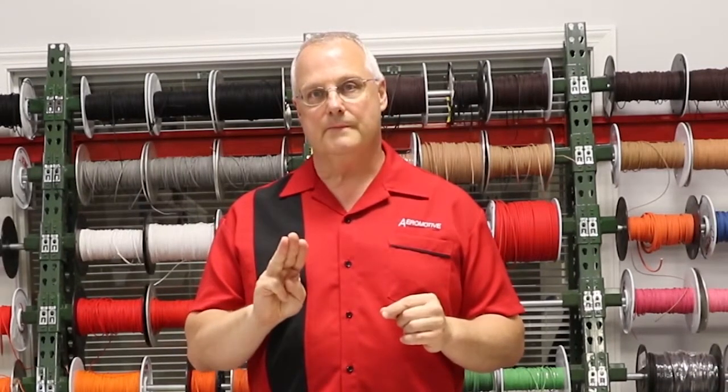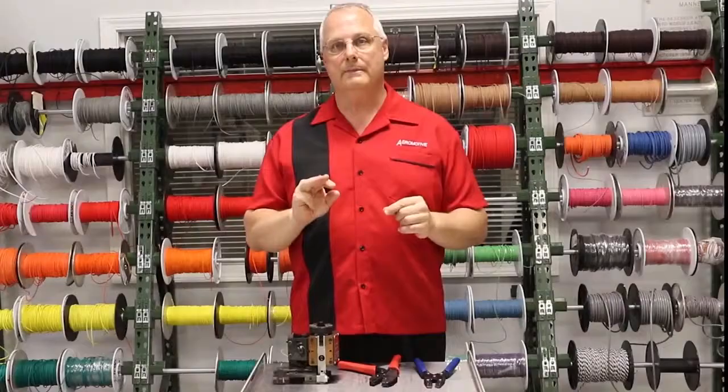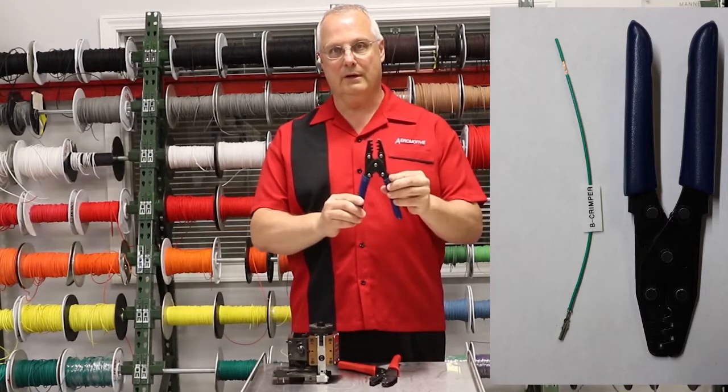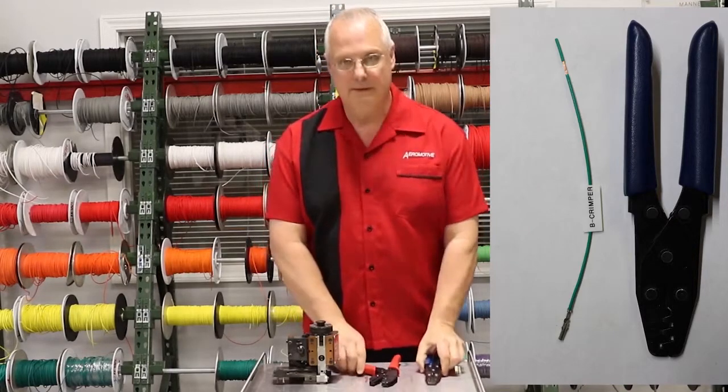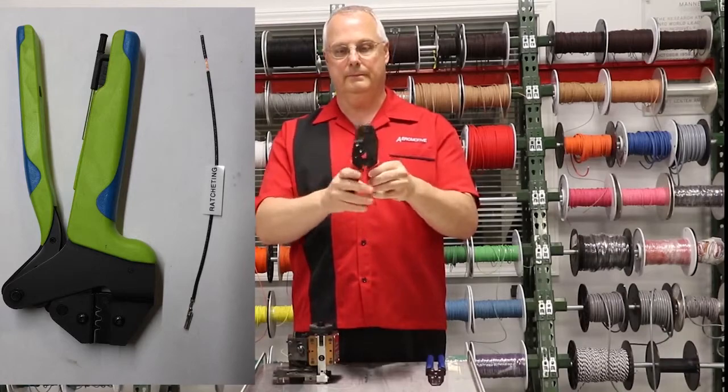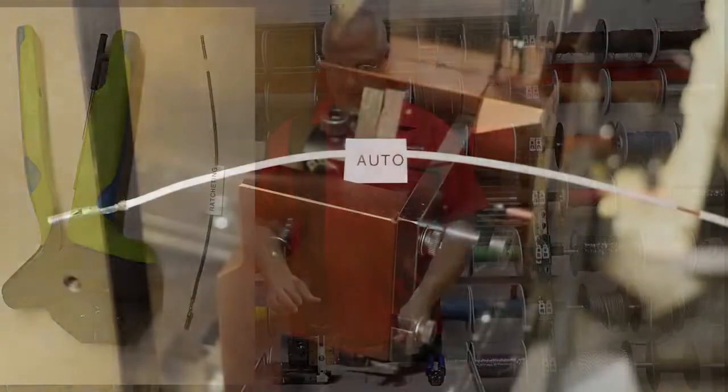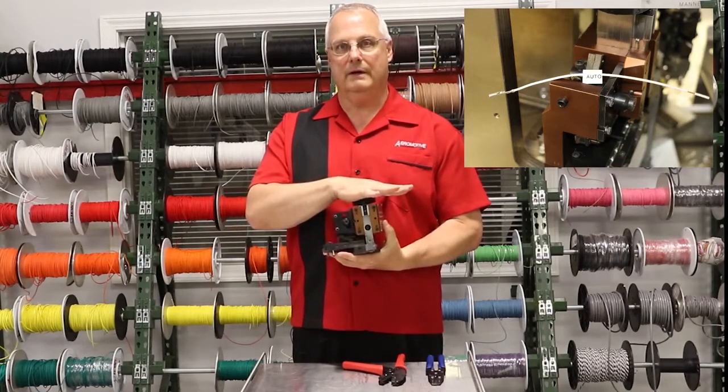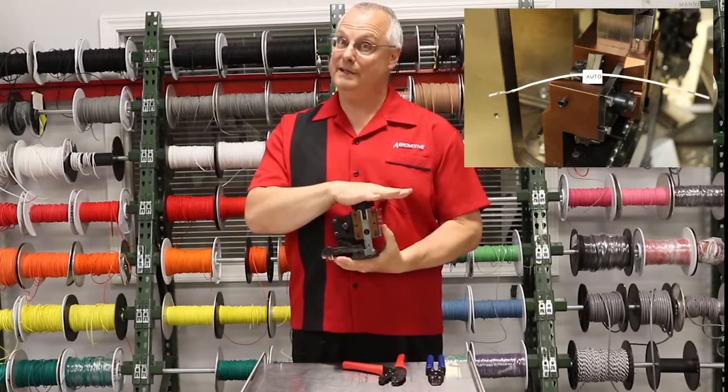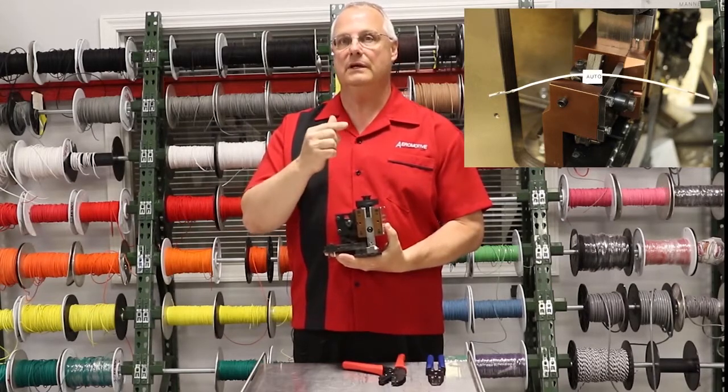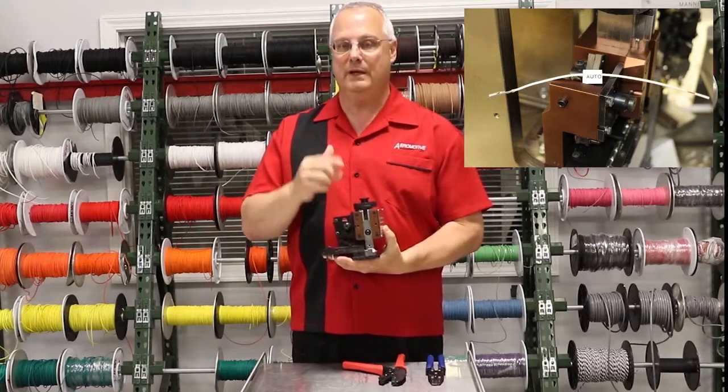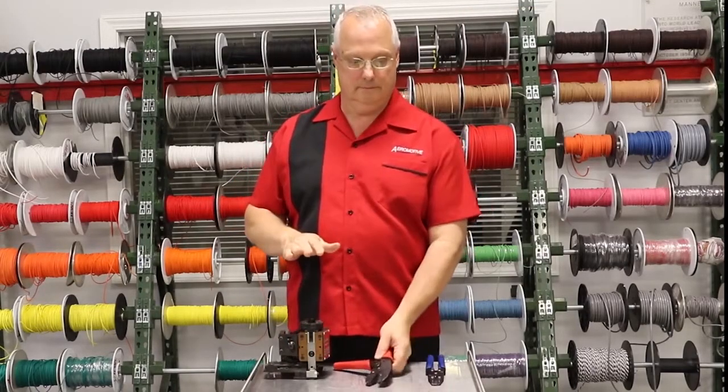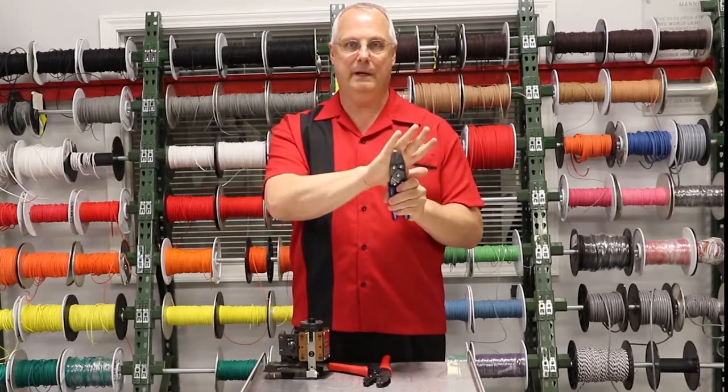We're going to look at three different types of crimps and test their pull strength. The first one we're going to look at is the standard B crimper used quite often in the field. The next one is your ratcheting type crimper, and third we're going to take a look at the auto feature. Highly recommend it whenever possible. Obviously you can't have one of these in the field, but at least we'll give you an idea of the difference between OEM quality, better tooling, and basic hand crimping.